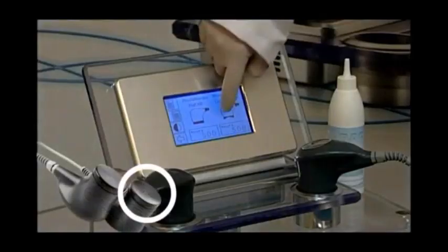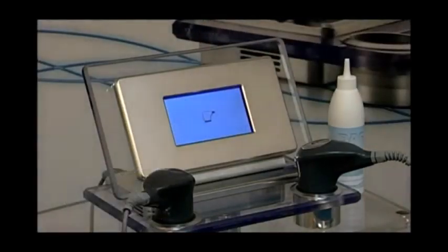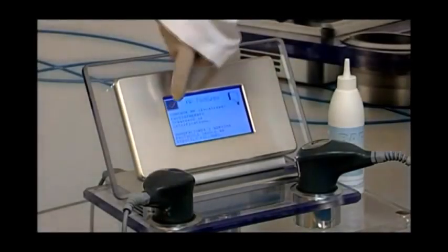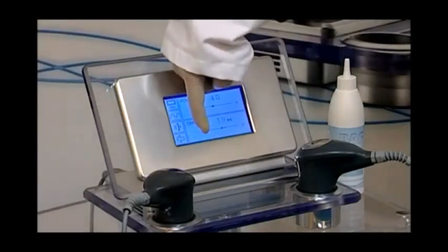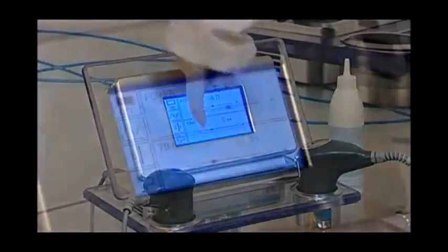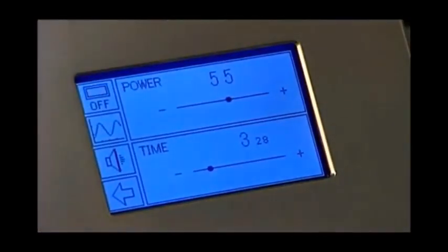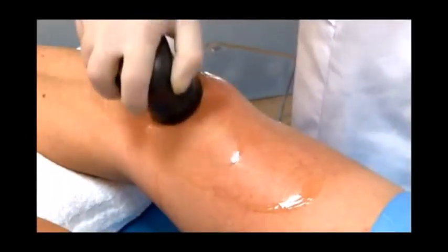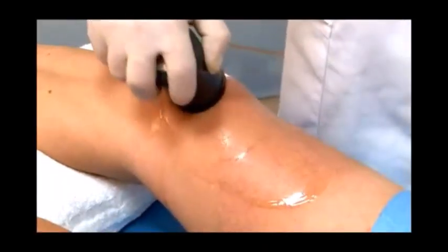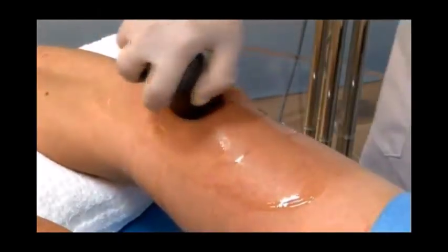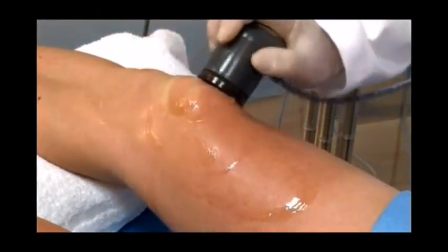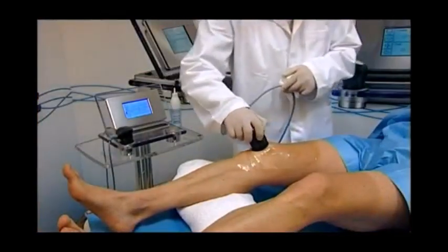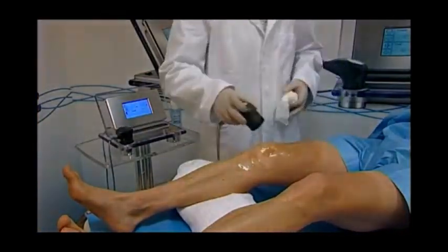Calibrate the concave hand probe and confirm. Set treatment time to 5 minutes. Set power output at about 10% less than what was set for the flat hand probe. Spread the gel on the area to be treated. Put the hand probe on the knee and slide the hand probe with circular movements. Apply enough pressure so that the concave surface of the hand probe comes in contact fully with the surface to treat. When treatment is completed, carefully clean the hand probe.